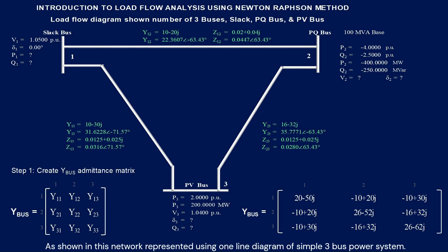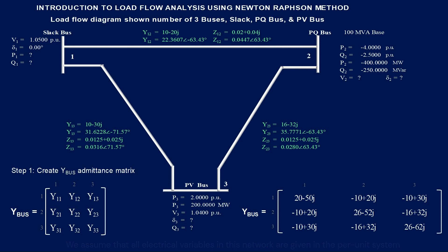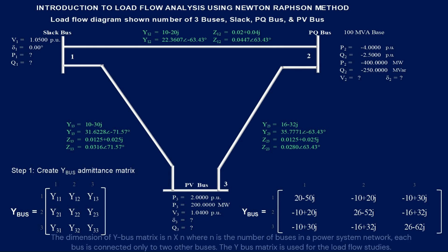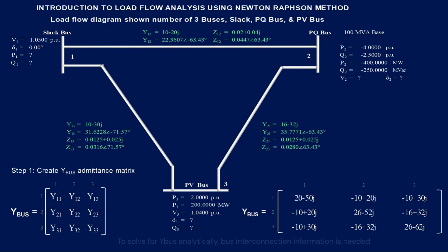As shown in this network, represented using a one-line diagram of a simple three-bus power system, we assume that all electrical variables in this network are given in the per-unit system. Step 1: How do you find the Y-bus matrix? The dimension of the Y-bus matrix is N×N, where N is the number of buses in the power system network. The Y-bus matrix is used for the load flow studies. Y-bus is referred to as the admittance matrix — a mathematical representation of the network power flow model. To solve for Y-bus analytically, bus interconnection information is needed.